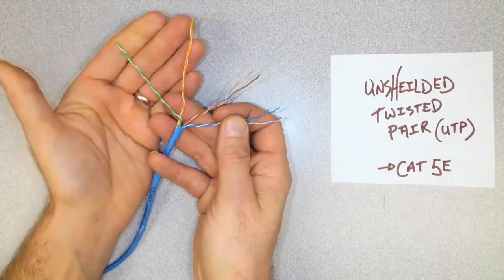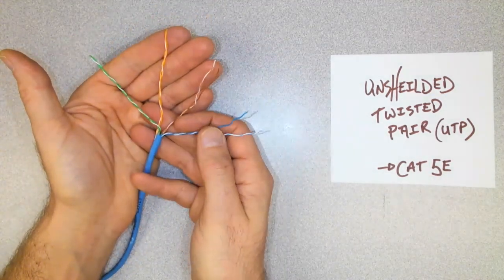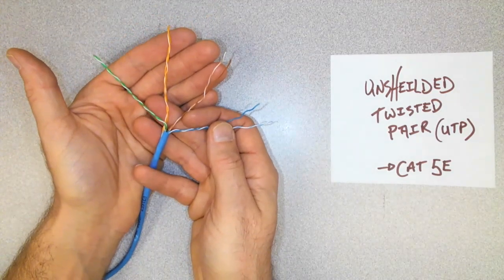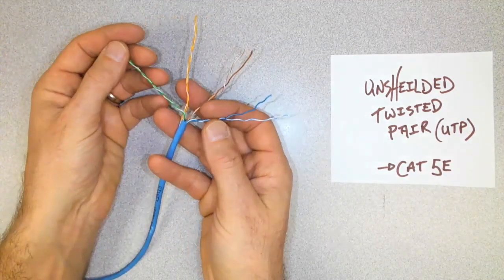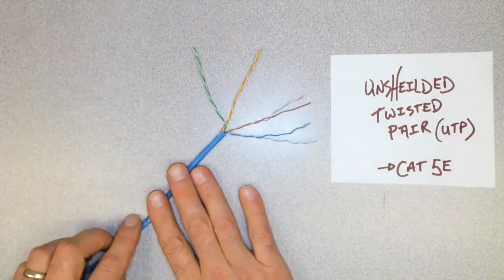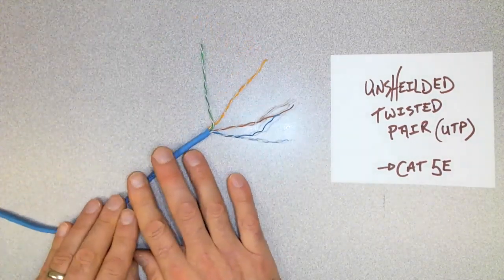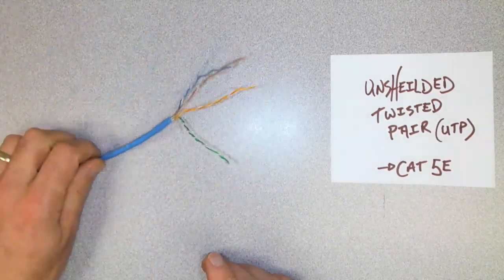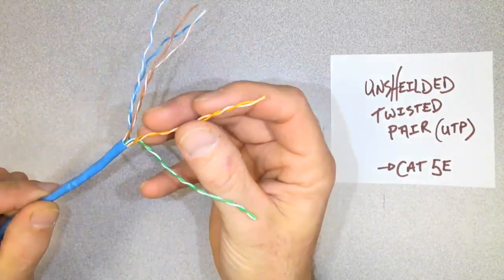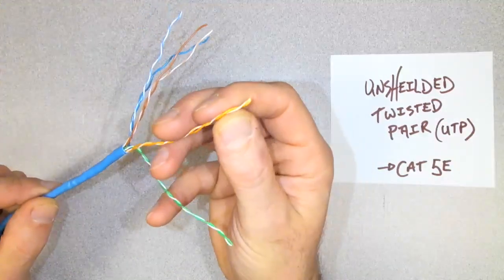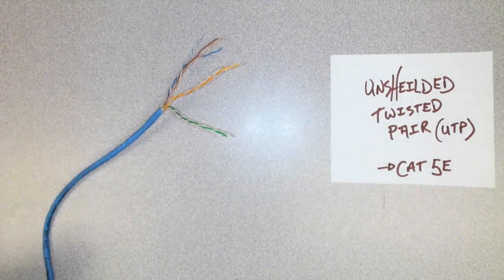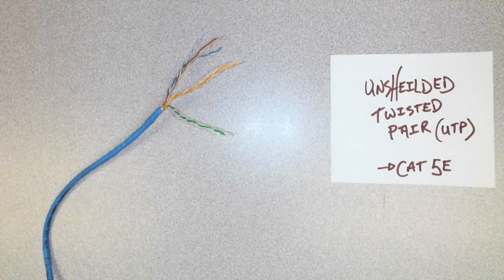Now, it doesn't matter if it's Cat 3, Cat 4, Cat 5, Cat 5A, Cat 5E, all of them have 4 pairs. And although historically it's been used for telephone and Ethernet connections, we'll find that the codebook is allowing for more applications that utilize this type of conductor for power over Ethernet applications. So section 16 will deal with this type of conductor being used, not just for telecom, but for actual installation that supplies power.